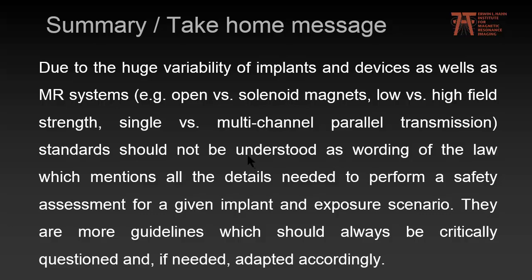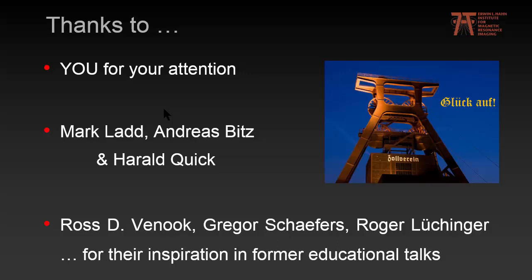In summary: due to the huge variability of implants and devices, as well as MR systems — open or solenoid magnets, low or high-field systems, single and multi-channel transmission systems — standards should not be understood as the letter of the law listing all details for a safety assessment. They are more like guidelines, and you should always critically question them and adapt them to your actual exposure or test scenario. Glück auf for your safety assessments. Thank you.